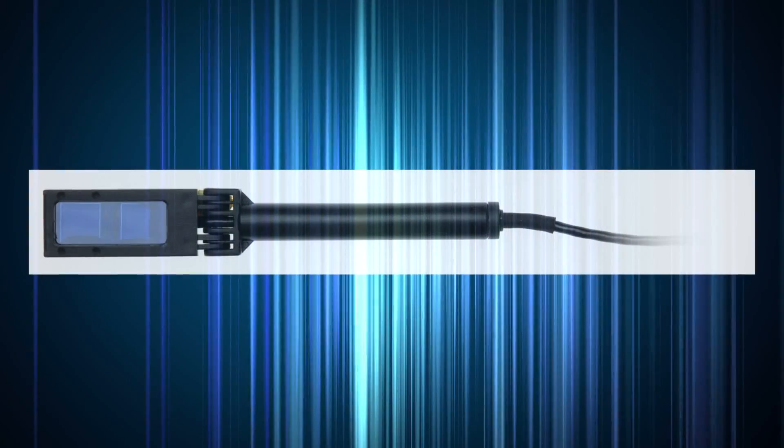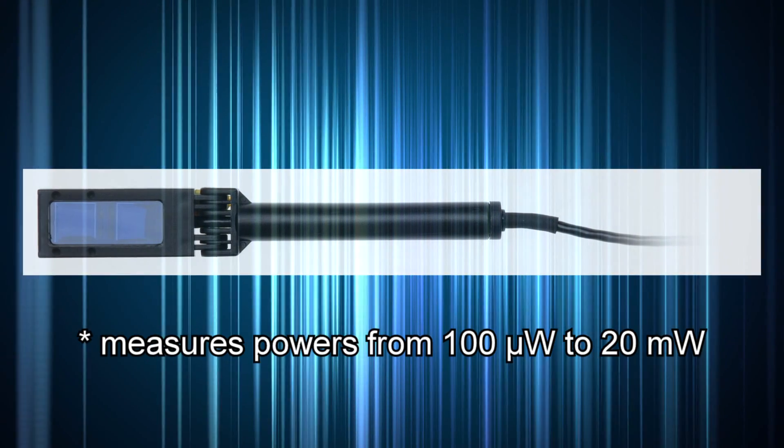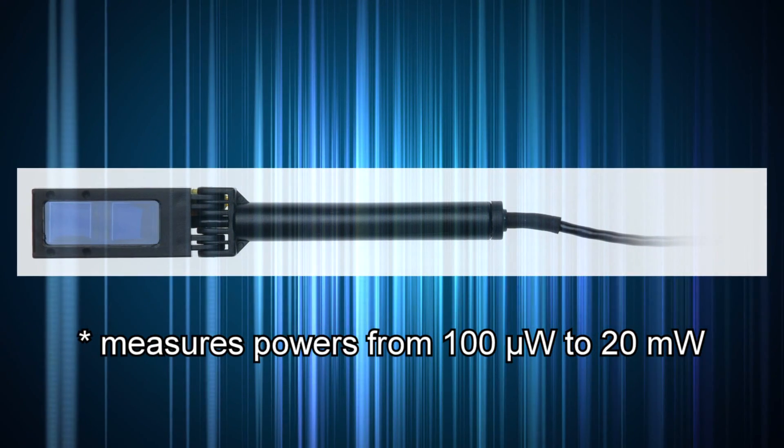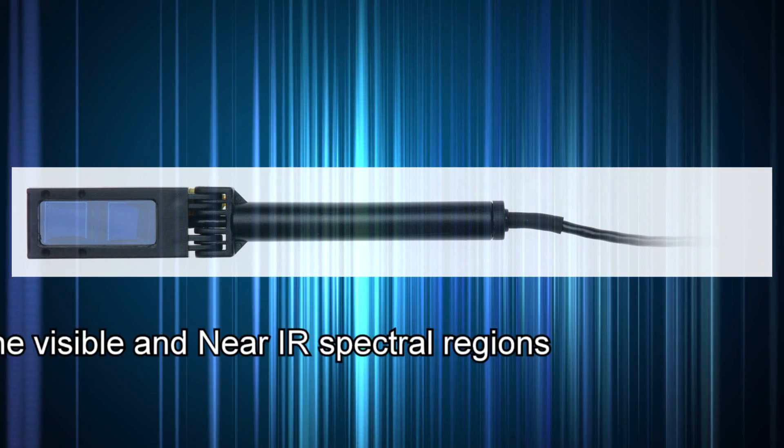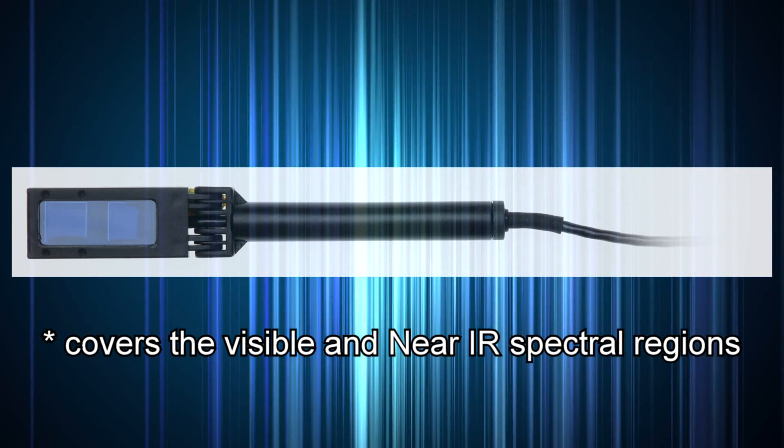For a scanned beam, this 13 microsecond minimum dwell time works out to a maximum scan speed of about 30,000 inches per second. The BC-20 can measure powers from 100 microwatts up to 20 milliwatts and covers the visible and near-IR spectral regions.